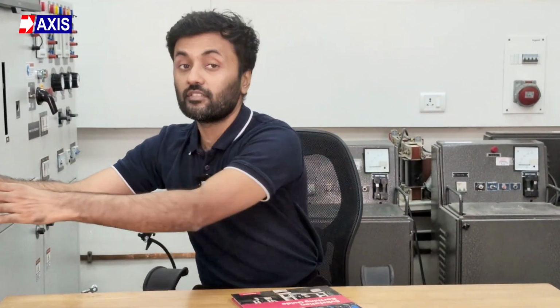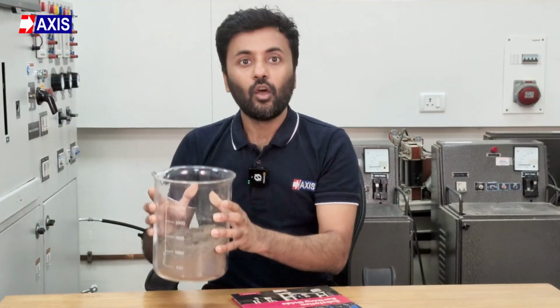If space is available, increasing the overall grid area reduces grid impedance directly, since a larger area means more soil contact and lower resistance. And if the soil resistivity itself is the problem, the material around the electrodes can be replaced with an earth-enhancing compound, such as this, which reduces the contact resistance between the electrode and the surrounding soil.